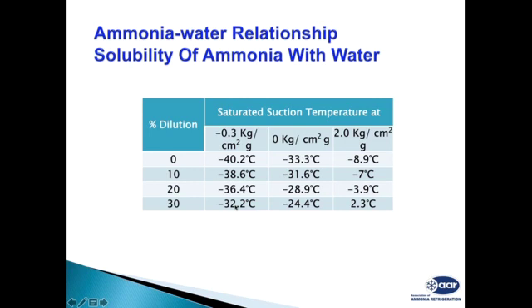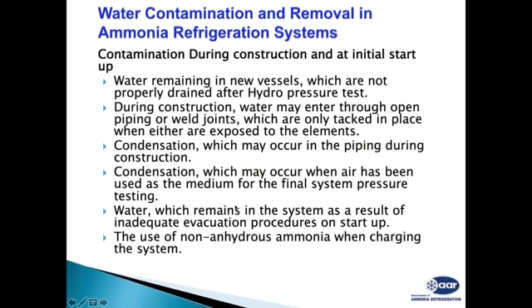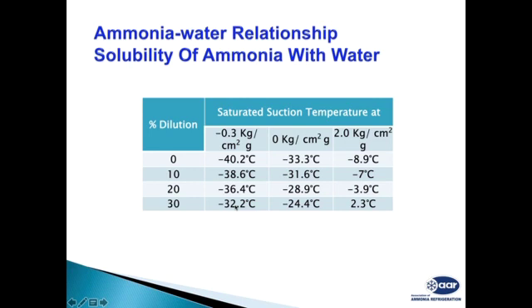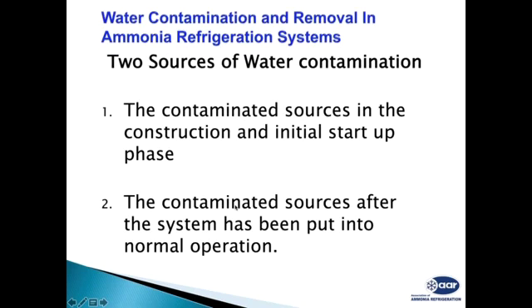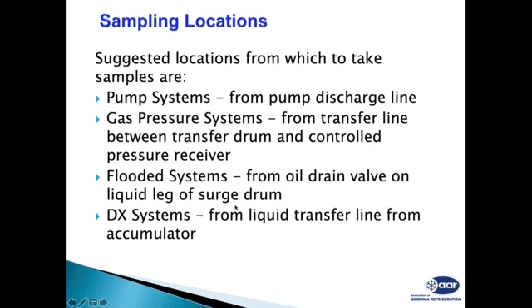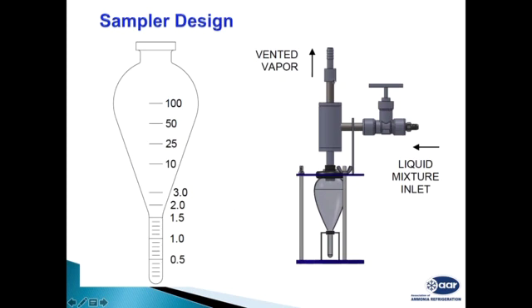See, I have already explained how to measure the water contamination. One is a very simple way. If your suction pressure and suction temperature do not match, like your compressor is running at 2 kg and you are not able to get the corresponding -9 degrees centigrade, and your suction ammonia temperature is much higher, then definitely you have water in the system. That's the first indication. And secondly, I have explained how to use this apparatus and how you take the sample into this. You can use this sampler to get the ammonia from the low side, let the ammonia evaporate, and what remains is the water.